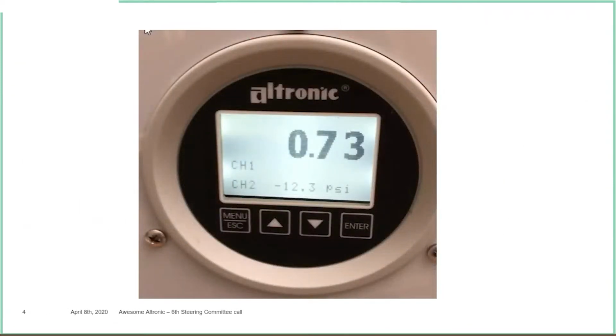This is actually a picture of the first prototype we installed. Some of you are probably really familiar with DSG products, and you can see this is a 2-channel. I just snapped a quick picture of it. What's nice is it has a large display, and the 0.73 pressure across that catalyst is in the range of half an inch tall, so it's easy to see. But that first one was a 1692 for a prototype. Then we did, like I said, switch up to the single point 1611 DSG, which I think in the end was a better way to go, because you not only have a 4 to 20 out, but you also have RS-485 communications. That's why that one has a 2-channel display there.